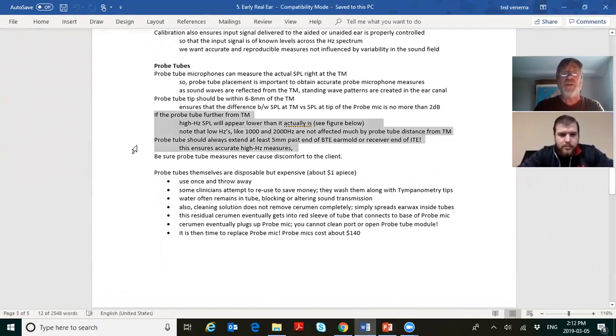The probe tube should always extend at least 5 millimeters past the end of a BTE ear mold or the receiver end of an ITE or past the dome. Now again, millimeters, centimeters, talking to Americans who are still using imperial, this is a centimeter. A millimeter is 1/10 of a fingernail. So essentially, make sure the tube is stuck that far past at least. That's one way of doing it. You can always do the bump and pull method too. Thunk, did that hurt? Oh, did that hurt? All right, I'm sorry.